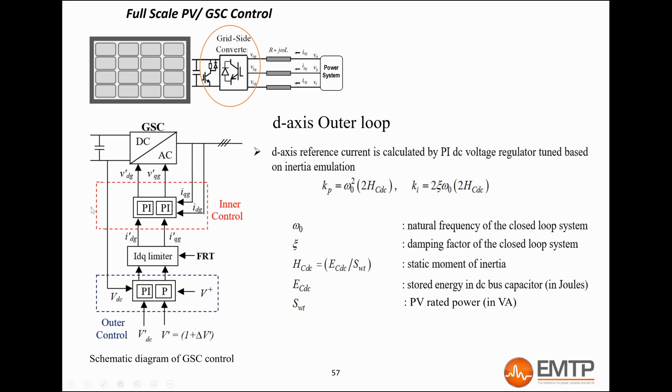The inner loop, which is the fastest one, produces the D-axis voltage reference to follow the current reference. Before being used by the inner loop, the current reference is limited by the IDQ limiter block, so the converter does not exceed its current capability, which could cause hardware damage. The limiter function will be explained later on in this presentation.